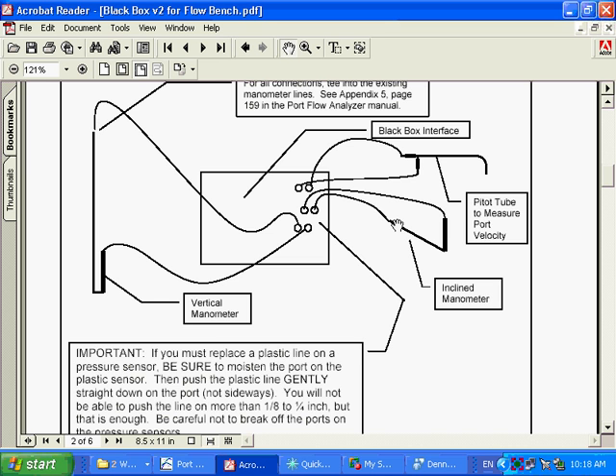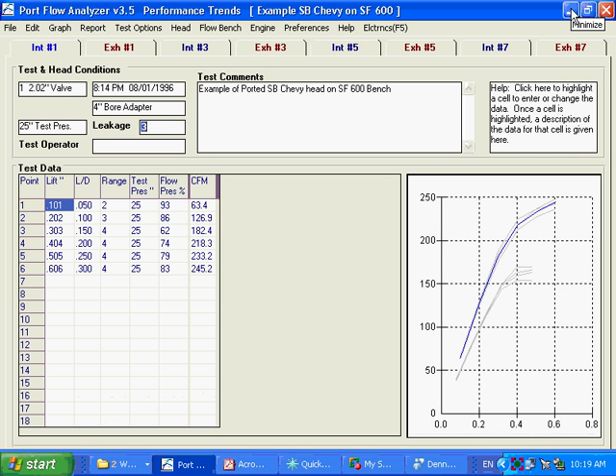Do the same thing for the incline and the pitot tube. Pitot tube, it may not even be necessary to have a manometer teed in with it, because the factory calibrations are going to be fine for a pitot tube because you're only looking for trends across a port typically. The incline manometer is very critical though. This one you must get calibrated as precisely as possible. The vertical manometer, where you said 10 inches or 28 inches or whatever, is not as critical as the incline manometer. So let's say we got our black box hooked up.